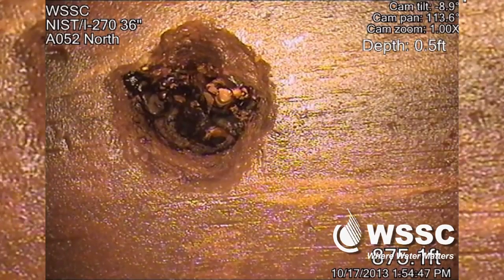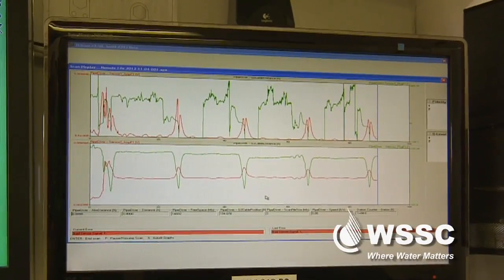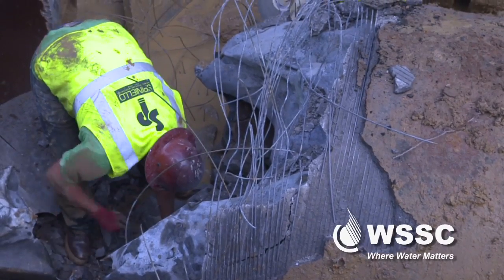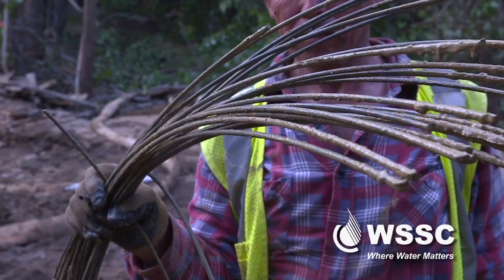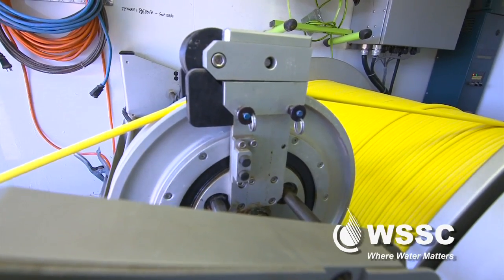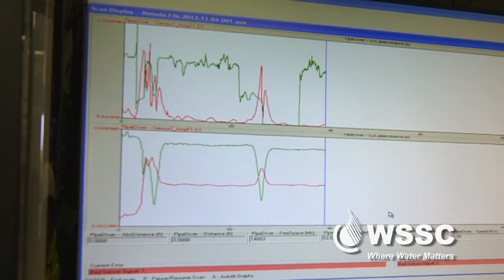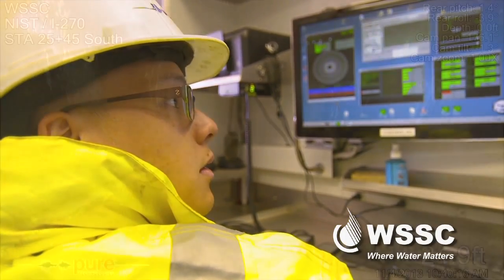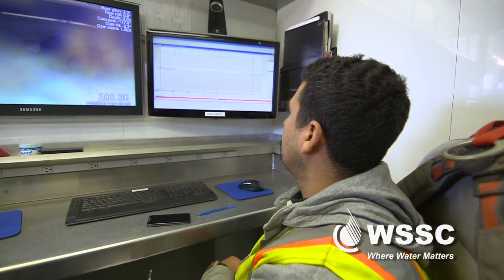In addition to visual, the robot also runs an electromagnetic inspection which provides vital stats on the pre-stressed wires inside the pipe. They really are literally the primary structural component of the pipeline — the reinforcement that provides the majority of the strength. This inspection technique puts an electromagnetic signal into the wires, and based on the response of those wires to that signal, it can assess the health of those wires and helps us establish a baseline to monitor from.